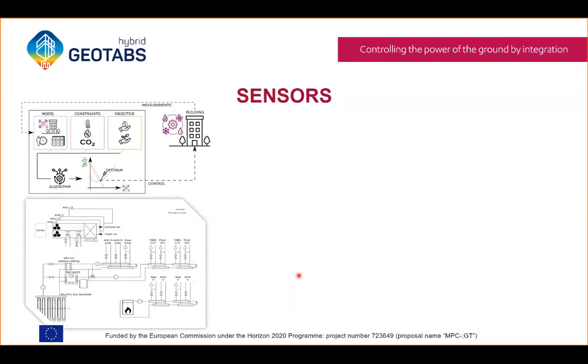Besides these hydraulic changes, I'd like to mention some points about sensors. I see an increasing number of sensors being installed in buildings, but not always the ones we need. A very important type are sensors for zones to measure comfort. Why? Because MPC will try to find the optimal point, the point where comfort is reached but energy or the objective is as low as possible. This is often just at the comfort boundary, which means there needs to be good feedback from the real building to the model, to make sure there's no offset, that the model isn't 2 degrees off. Otherwise, you will cause discomfort. It's also simply important to have these sensors to evaluate comfort through the year in the building, to ensure the system is working well, regardless of the type of control installed.